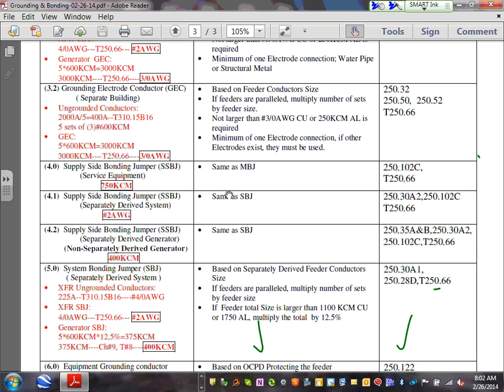So Karen, here are 3 conduits coming to the bottom of the switchgear. Can you guys see that? You take a wire, tie the first one to the second, to the third, and to the ground bar in this switchgear. Or you can home run them. Take one conduit, clamp on it, and tie it to the switchgear, then the second, then the third. 2 options. How do you size the supply side bonding jumper, guys? The supply side bonding jumper is sized exactly as the main bonding jumper. Same as the main bonding jumper.